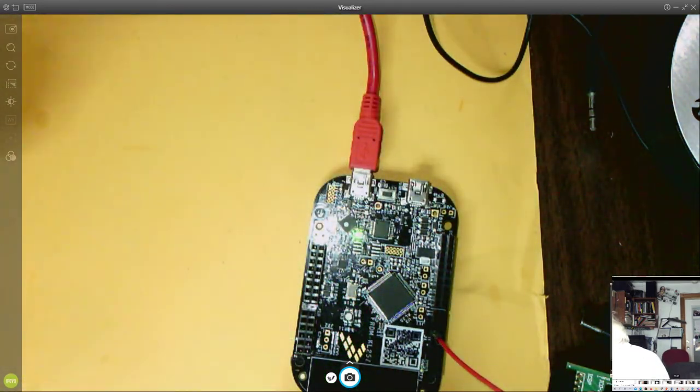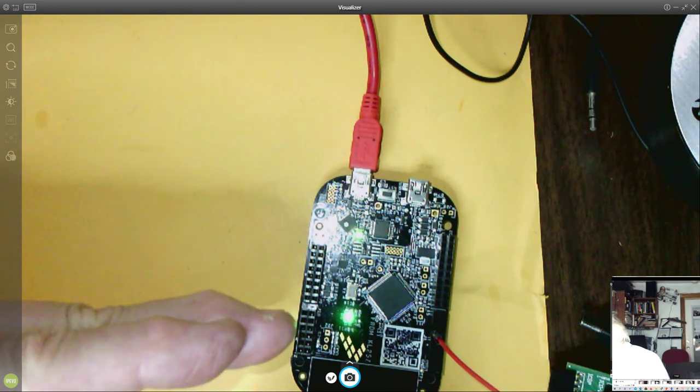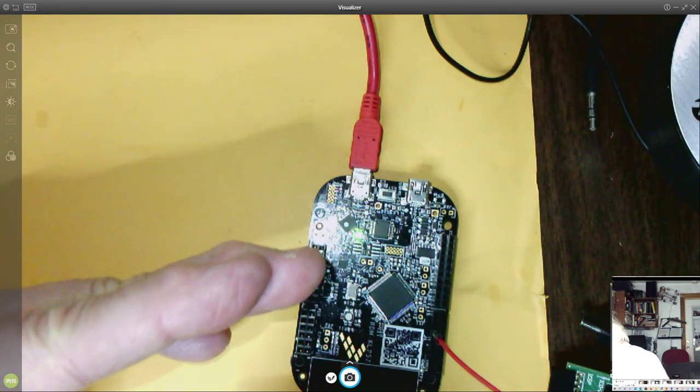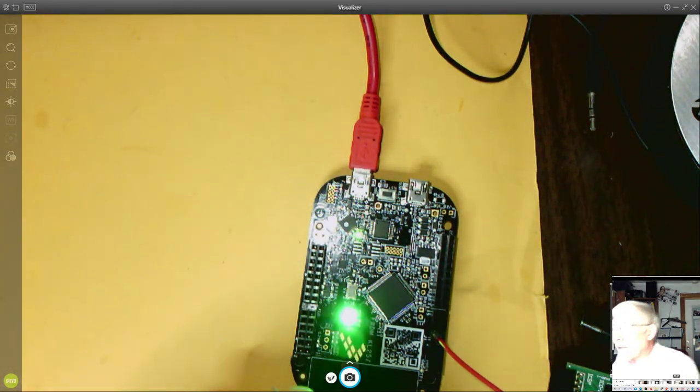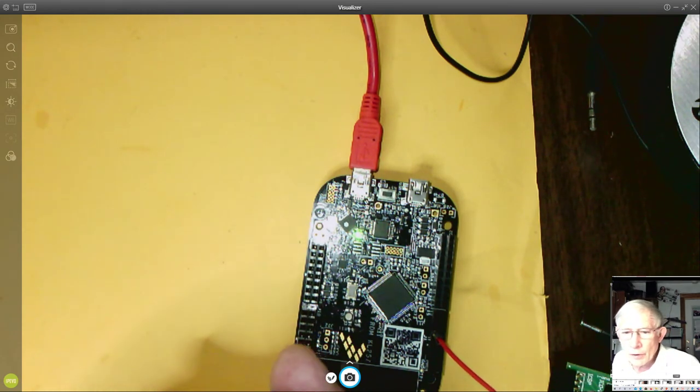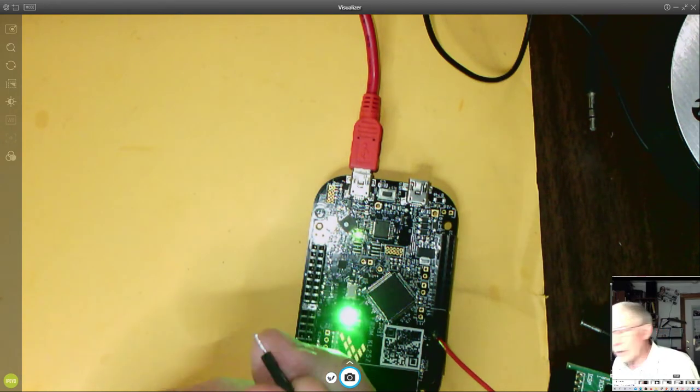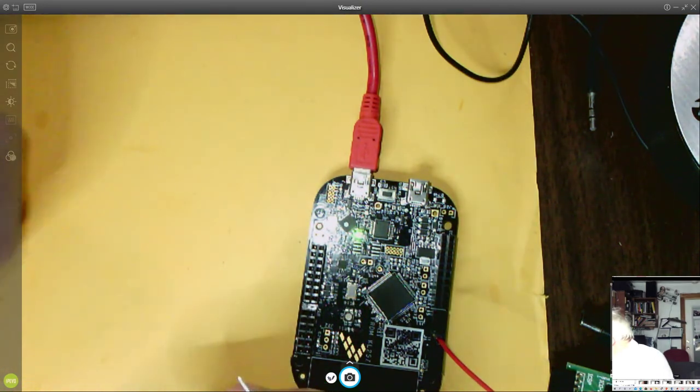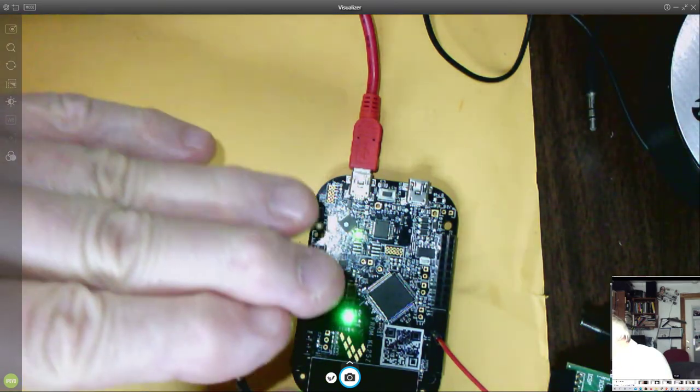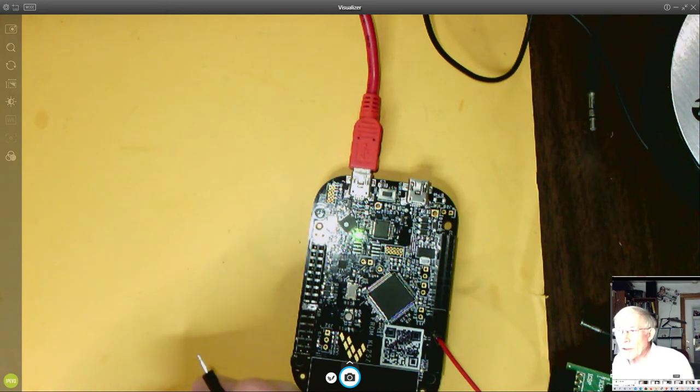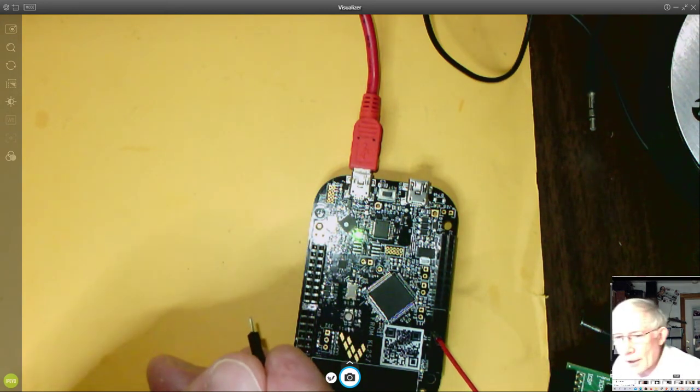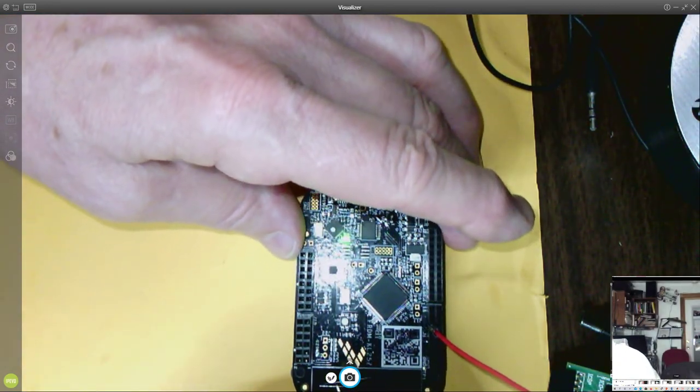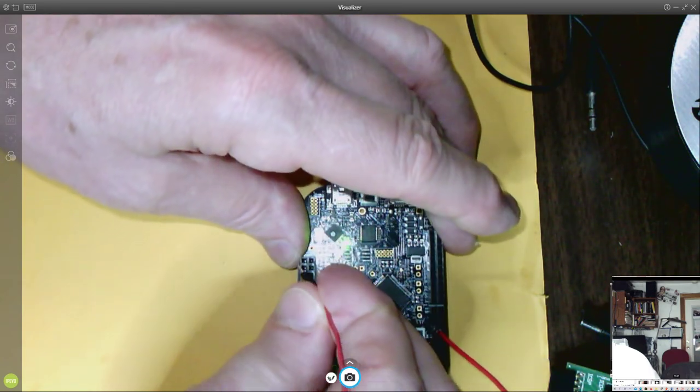On that floating input, as my hand has a little bit of electrostatic charge on it, it induces a voltage. That's because that input is so high impedance that it takes very little current. It's very sensitive and it definitely can detect electrostatic. You can also probably get the opposite effect. Remember, that's because this is an analog input. Our digital inputs don't behave this way, they're much more robust.